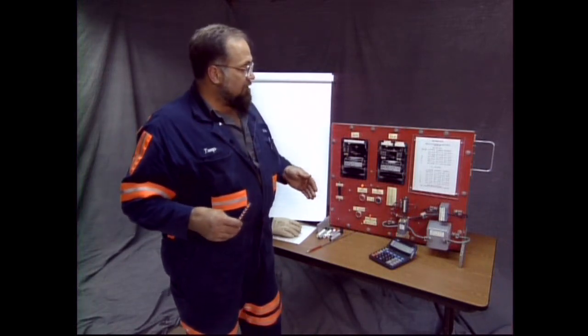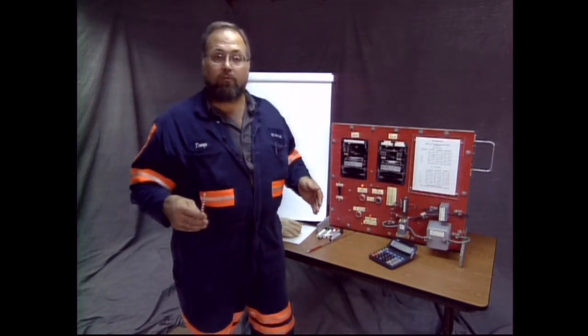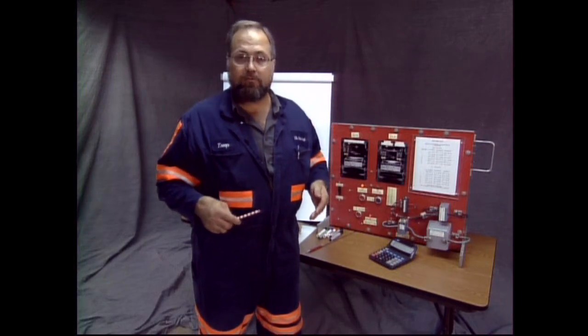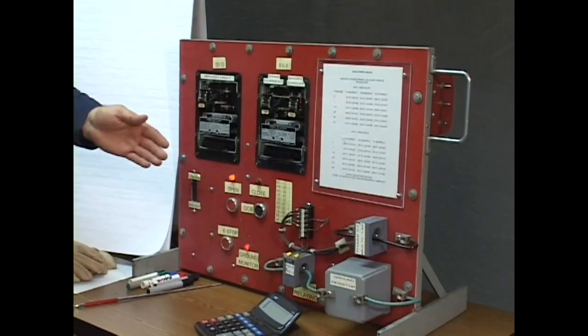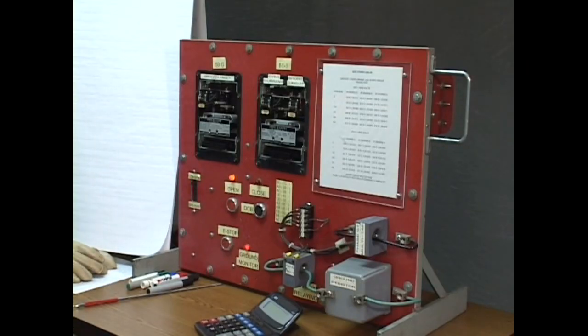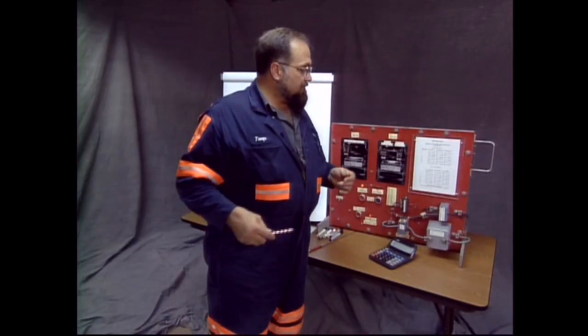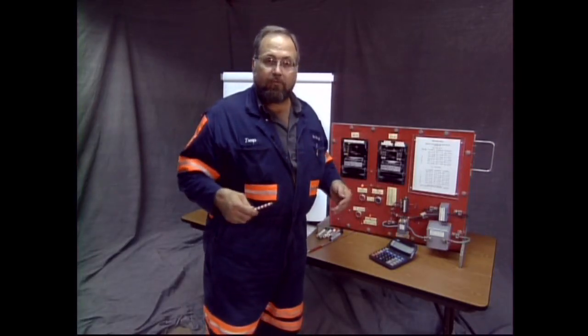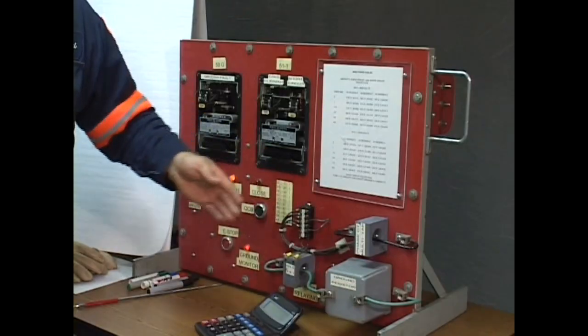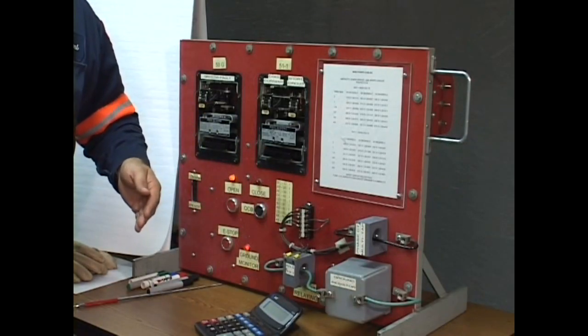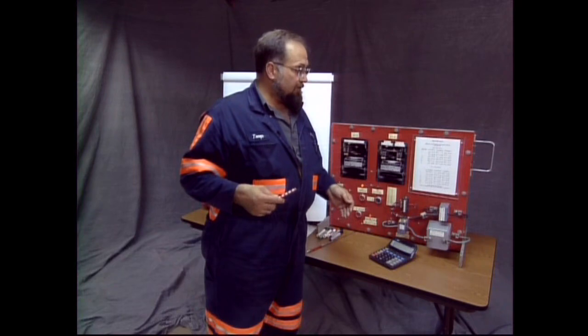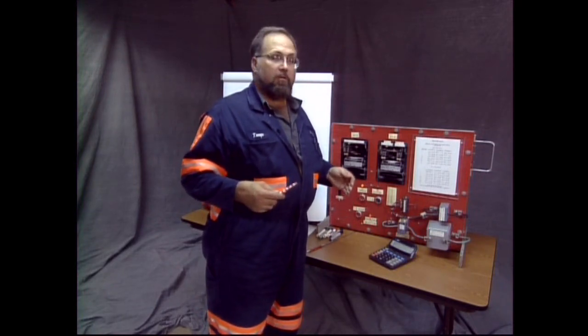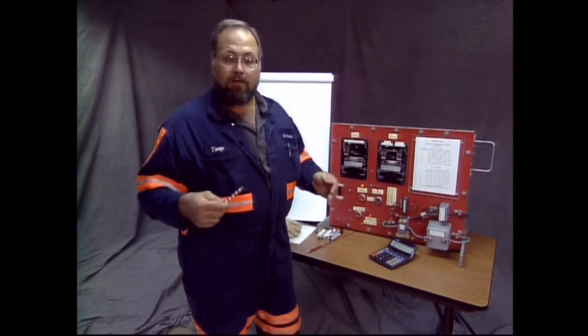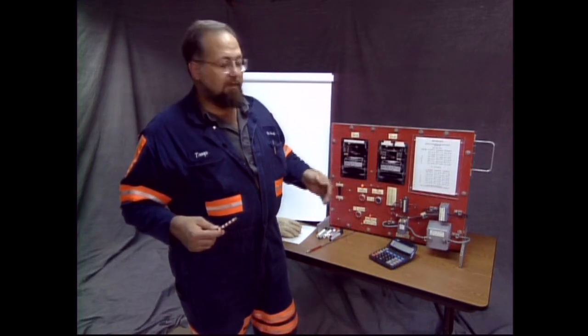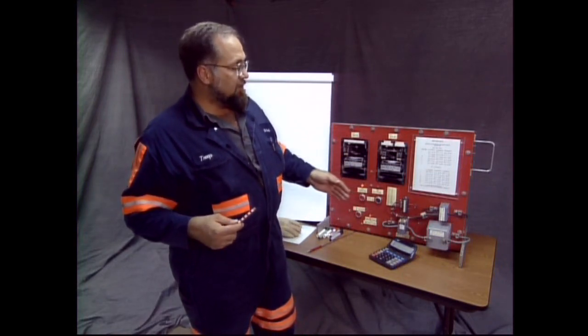You might be asked, what's the maximum voltage allowed external to the ground resistor in the event of a ground fault? It's 100 volts. We figured one ground resistor here earlier. You can be asked, what's the industrial standard for the ampacity secondary of a CT such as this? It's 5 amps. That dictates the upper level tap setting for us, 5 amps, the ampacity of this CT.